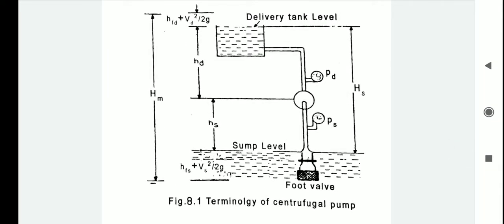The fourth part is manometric head. It is the total head or lift that must be produced by the pump to satisfy the external requirements. It includes all the losses like frictional losses, leakage losses, etc. If there are no losses in the impeller, then the manometric head will be equal to the head imparted to the liquid by the impeller, that is Euler's head.